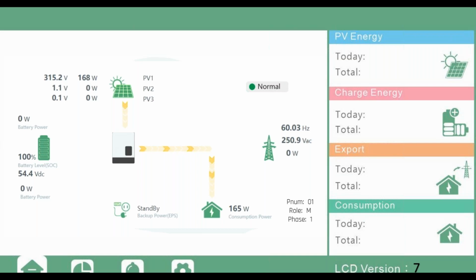But let's start with the home screen of the inverter. You see the power flow, and then you're going to notice here the number. The product number, or the inverter number, is going to be 1. And then it's going to say role, and it's going to say M for master, and then what phase it is. So here we can see that it seems almost like a fast zero export application, since there's PV production going into the loads, the battery is 100% charged, and it's not exporting to the grid.